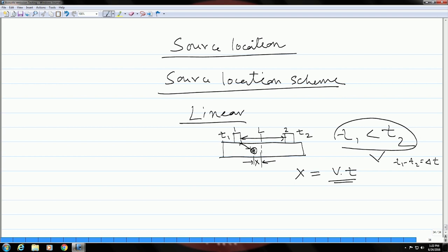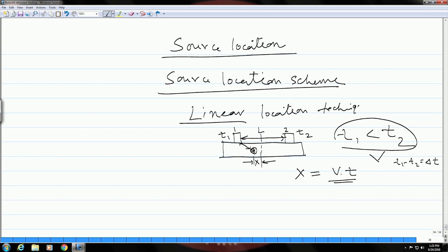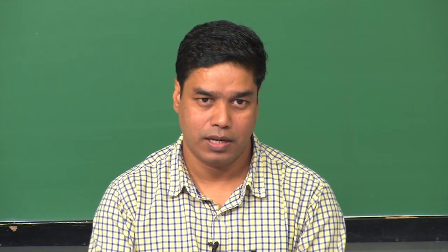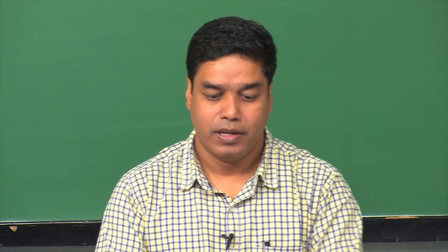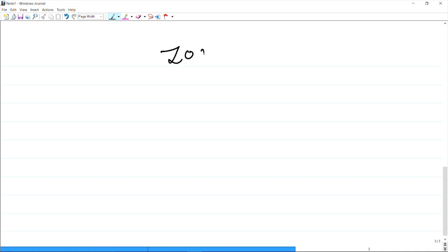This is the linear location technique, but for complex geometry or structures that may not be exactly linear, this kind of linear location technique cannot be used. If you have other complex components or structures to be inspected and want to get some idea about the location of the sources, you have to use the zonal location scheme.